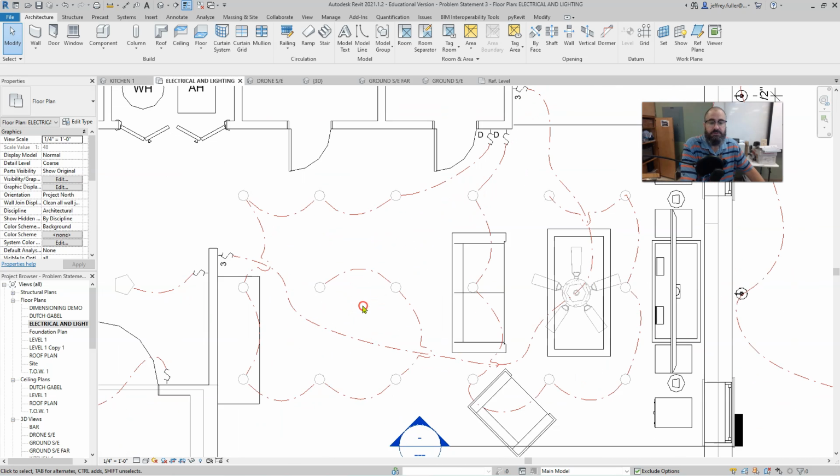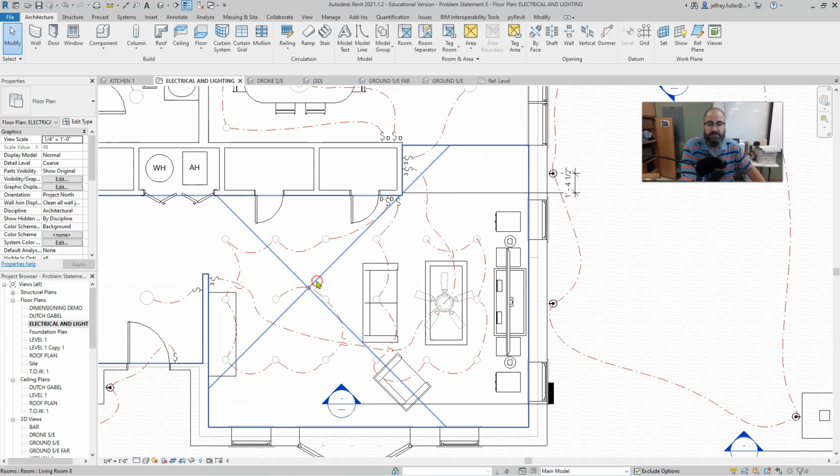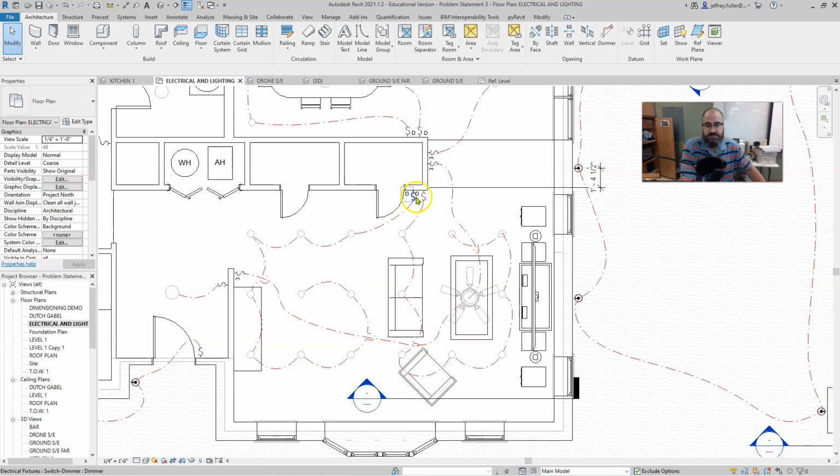Now, again, I showed you a little bit of how I did my living room, from the switch to the fixtures that switch is going to control. In this case, with this bank of recessed cans, I run the wire to each recessed can and then run it to the very last recessed can. I do not run that back to the switch. And I also don't run separate lines from the switch to each individual light fixture. I've seen people make that mistake before. Okay, but if a switch is controlling several light fixtures, it's just a path from the switch to each light fixture and then ends at the very last light fixture that it controls.